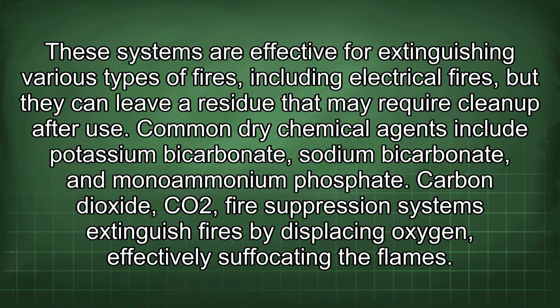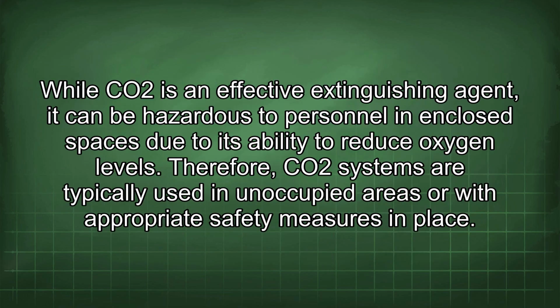Carbon dioxide, CO2, fire suppression systems extinguish fires by displacing oxygen, effectively suffocating the flames. While CO2 is an effective extinguishing agent, it can be hazardous to personnel in enclosed spaces due to its ability to reduce oxygen levels. Therefore, CO2 systems are typically used in unoccupied areas or with appropriate safety measures in place.